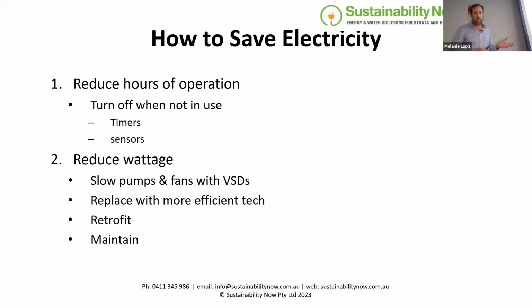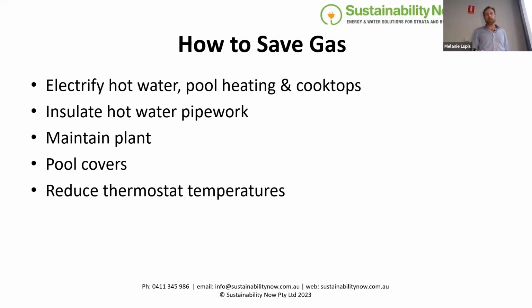So slowing the pumps and fans with VSDs, replacing them with more efficient technology. Just buying a modern electric motor now, it's probably 40% more efficient than it was 10 or 15 years ago. The general technology in these things is much better than it used to be. There's a thing called MEPS, Minimum Energy Performance Standard, so they're constantly getting more efficient. Retrofitting and doing your general maintenance: things will always run more efficiently if you maintain them as per the manufacturer's guidelines.